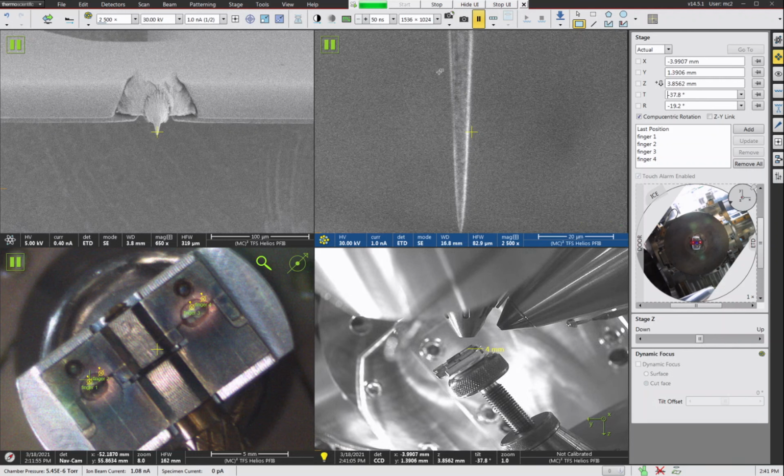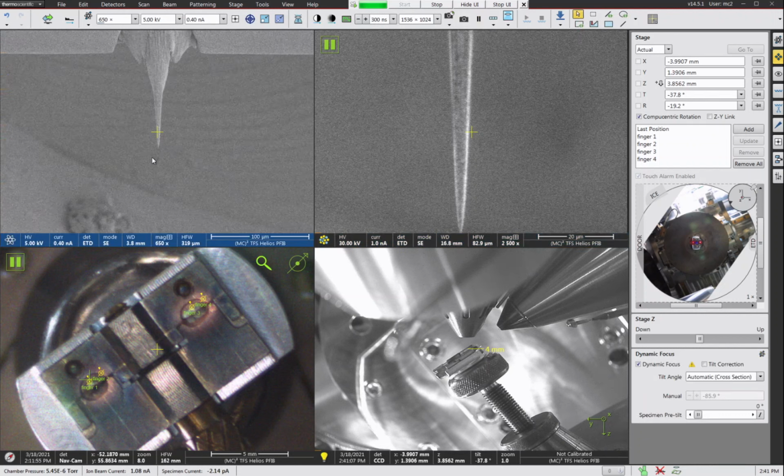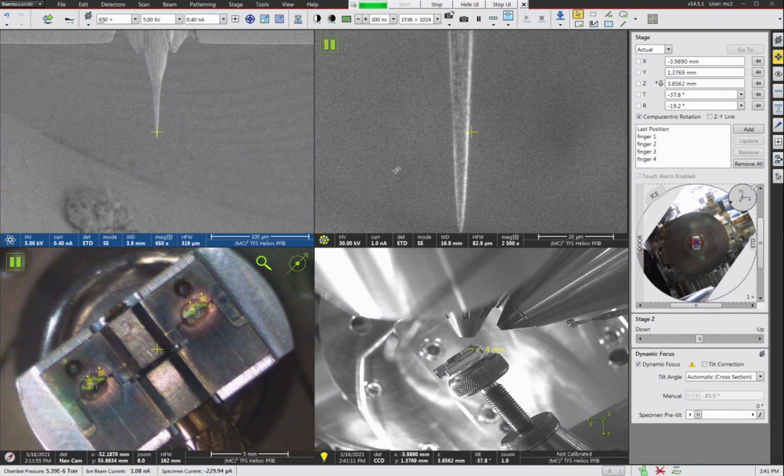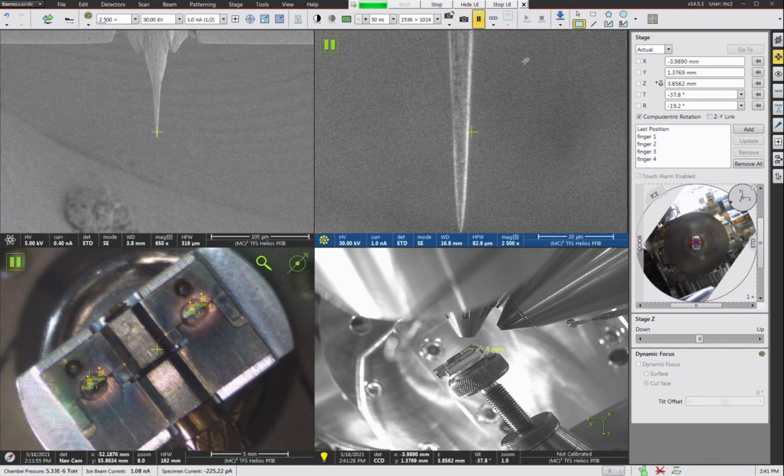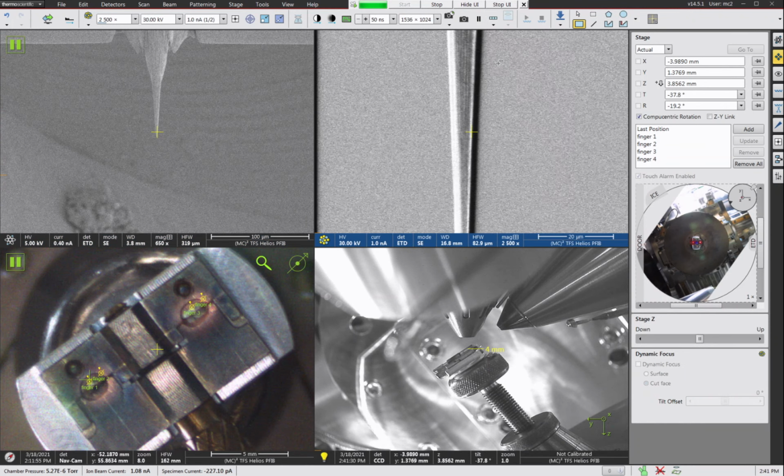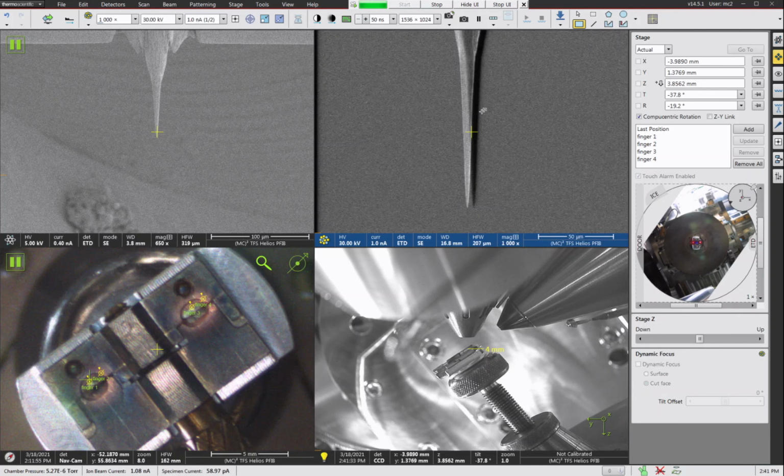Now, there is a really, really important safety concern here. For some reason, when ThermoFisher wrote this software, they didn't think about the fact that in the FIB image, if you double click, the stage tries to move really, really fast, either away from the FIB or towards the FIB. And you've got to be really careful on this. So if you're looking at your FIB image like this, keep in mind that the axes haven't moved around.